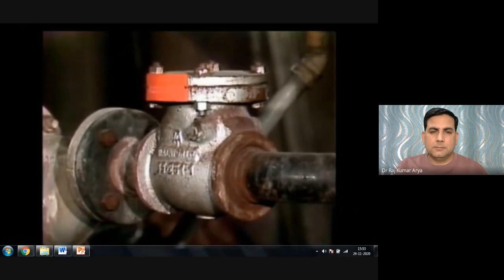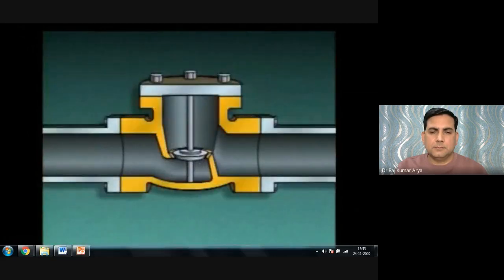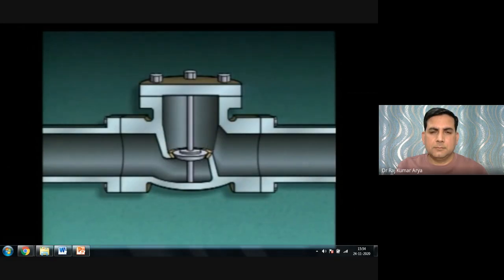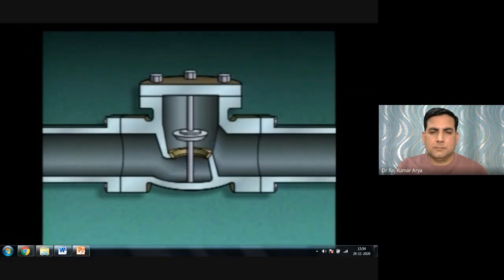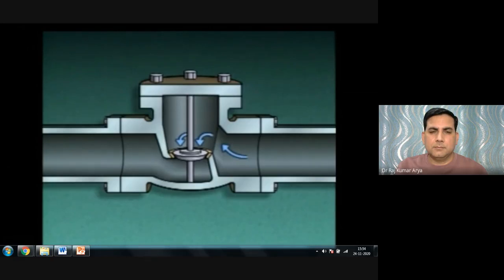A lift check valve consists of a valve body, a disc, a seat, and a guide. The guide keeps the disc aligned with the seat during operation, ensuring the disc will seat properly when the valve closes. When fluid flows, the disc lifts. When flow stops, gravity pulls the disc back onto the seat, and backflow pressure pushes it tight. Lift check valves can be used in either horizontal or vertical piping runs.